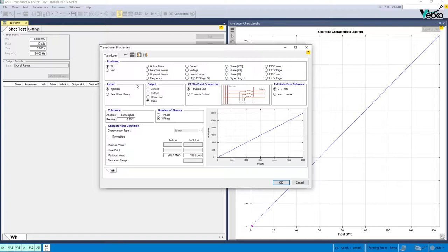On the other side, the transducers can also have binary outputs which are activated as soon as the specified characteristic goes past a certain limit. In some other cases, it's possible to use the output binary signals as a counter that produces a pulse based on the measured energy. The type of output received from the transducer is specified in Output section.